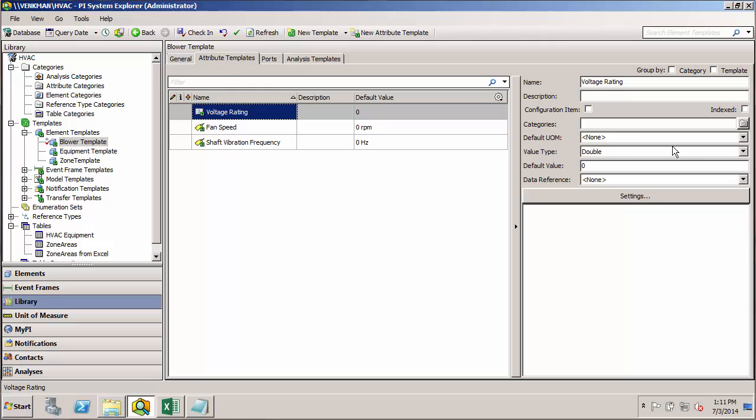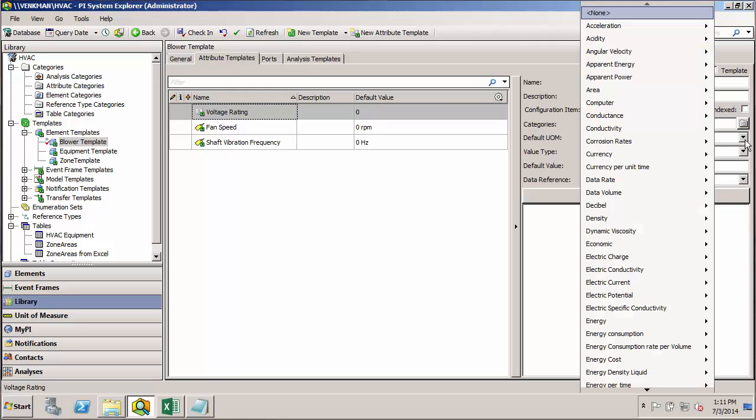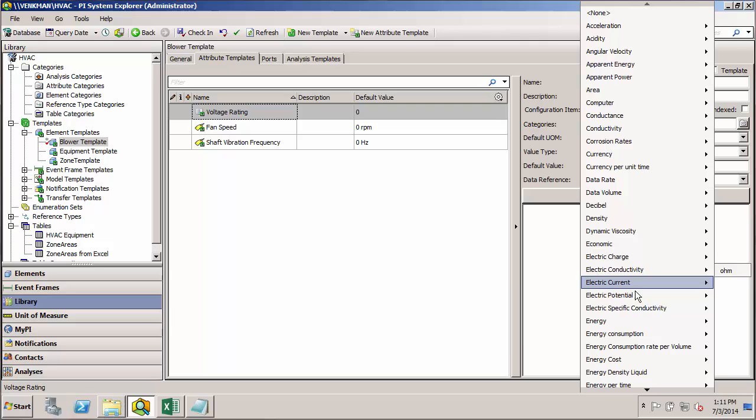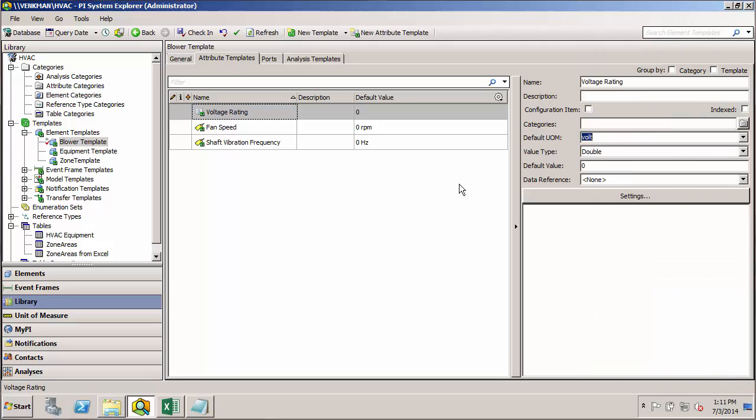So in order to do this, we just need to make sure our new attribute has the exact same name as the one in the parent template. So it's going to be voltage rating. And we'll make sure we have the same units of measure, electric potential, volt. And then for the default value, we're going to put in 460 for a blower. So now any time I build a blower off of this template, it'll have a voltage rating of 460.